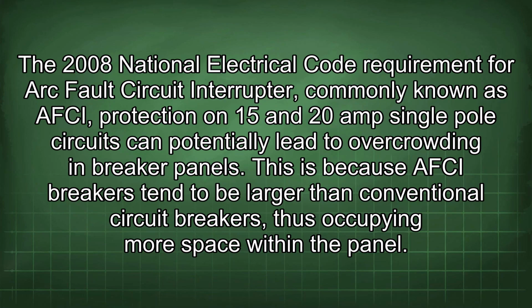The 2008 National Electrical Code requirement for arc fault circuit interrupter, commonly known as AFCI, protection on 15 and 20 amp single pole circuits can potentially lead to overcrowding in breaker panels. This is because AFCI breakers tend to be larger than conventional circuit breakers, thus occupying more space within the panel.